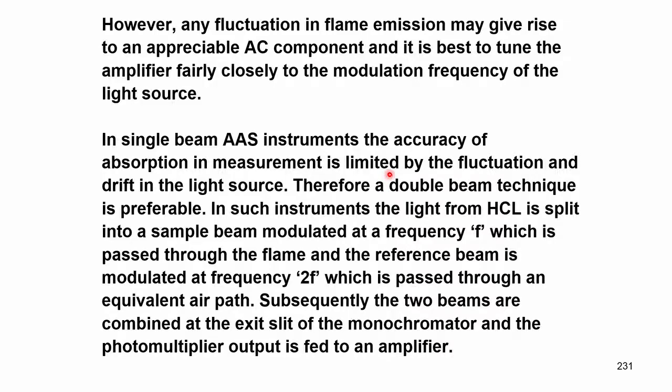Therefore, 99% of the atomic absorption spectrometers nowadays are double beam instruments. Sometimes, even with single beam instruments, the information is stored in the computer, and once it is stored, you can perform other analysis and compare it to the standard value stored in the computer memory.